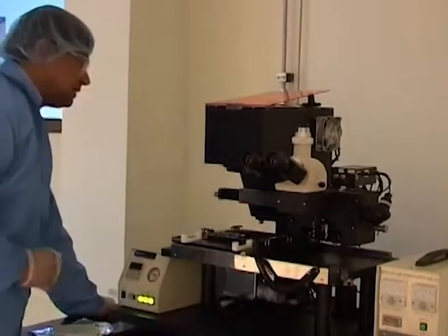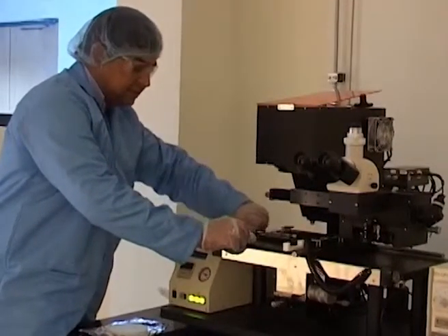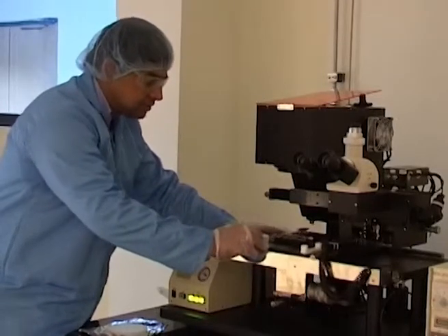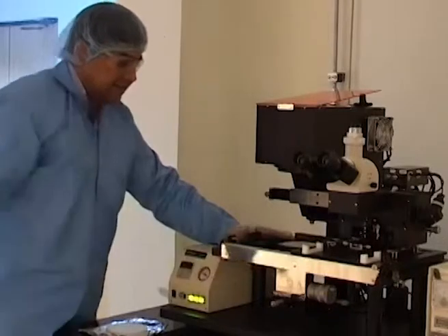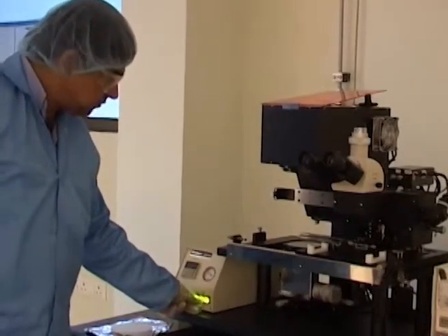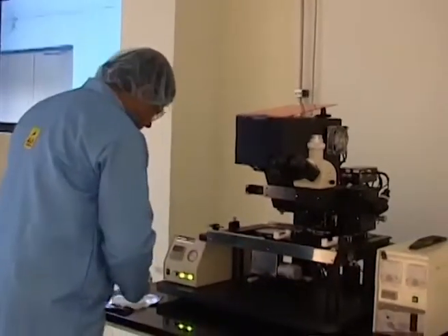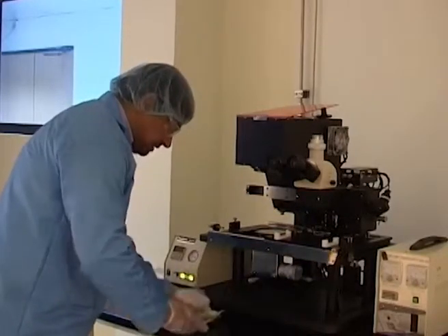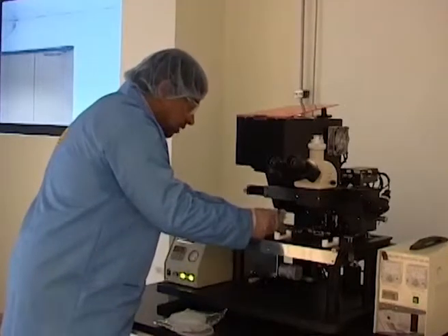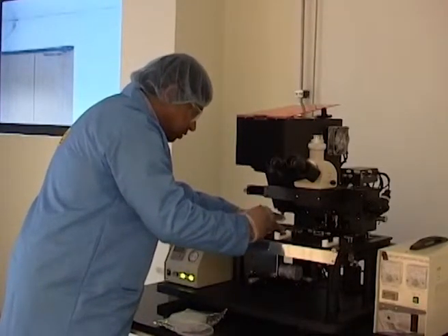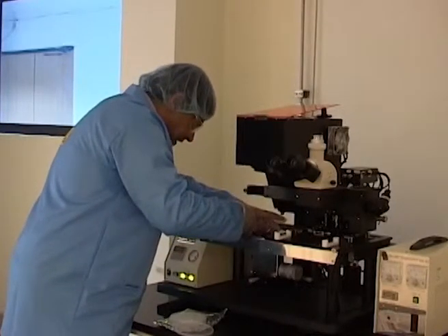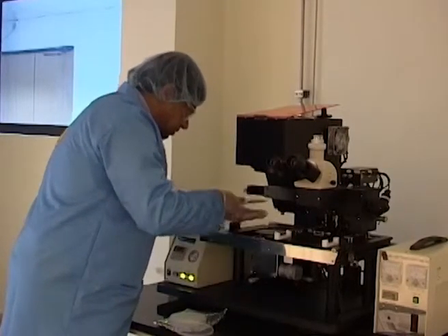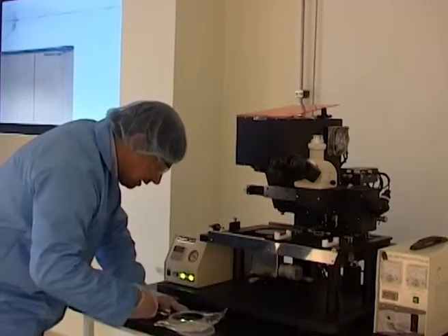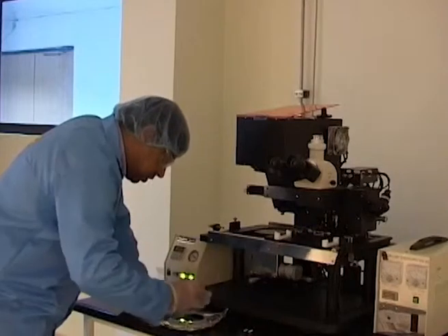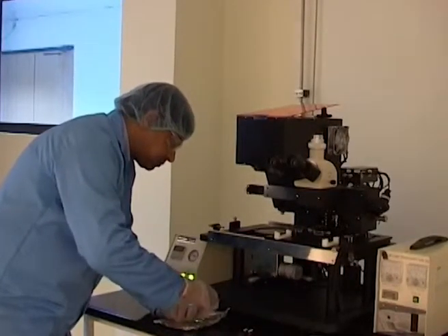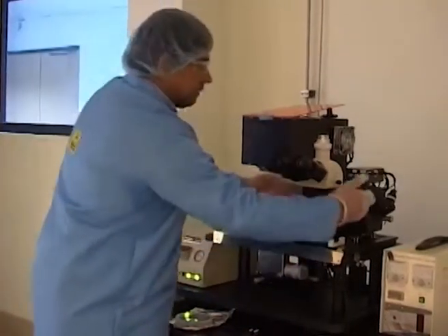The next step would be to push back the mask holder all the way back to its resting zone, which is close to this end, and turn off the wafer vacuum so that I can pull out the wafer, and this is the exposed wafer which we are pulling out. We'll load it back into its resting place, which is this container right here, and we will do something called post-exposure bake after this step. So slowly you have to pull out the wafer from its stage. Now it has been released, vacuum is no longer holding it, and you slowly take it and put it back into its wafer box, cover it so that there is not much dust contamination on the surface, close it, and set up the microscope back to its place here.